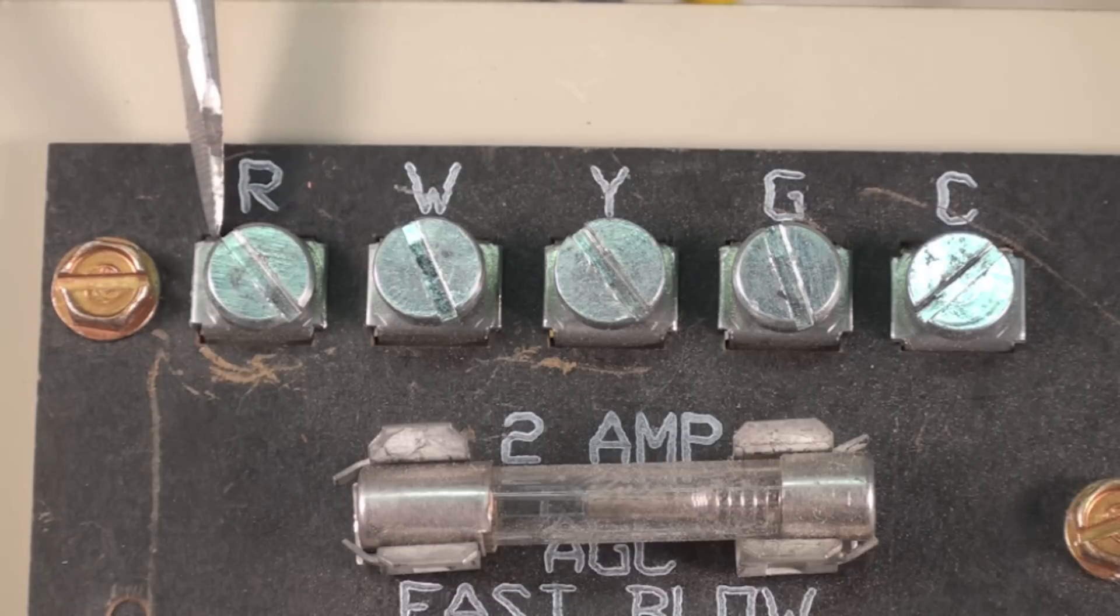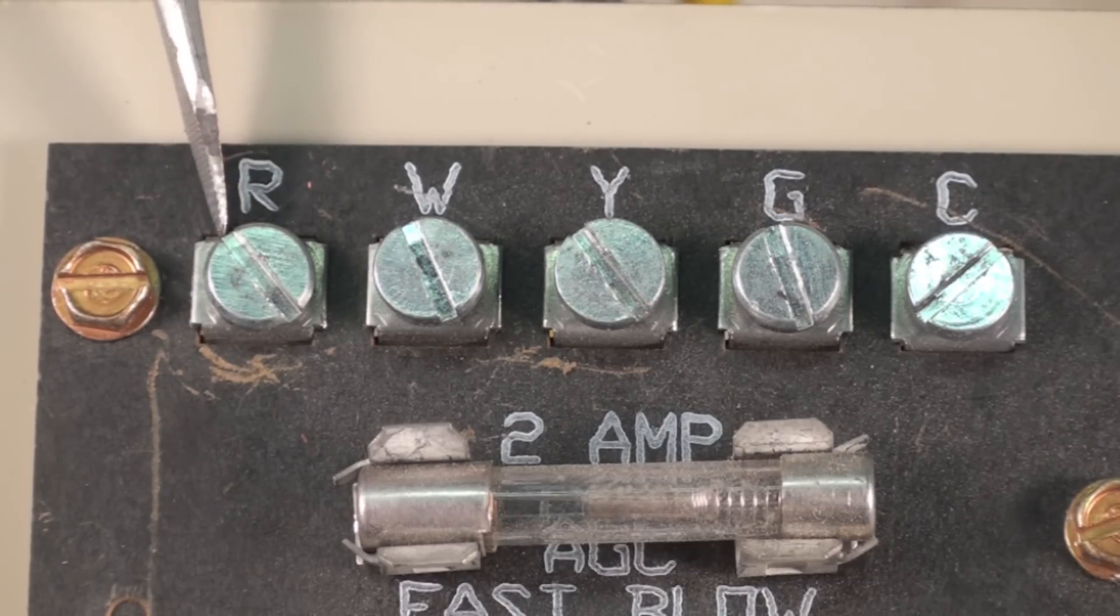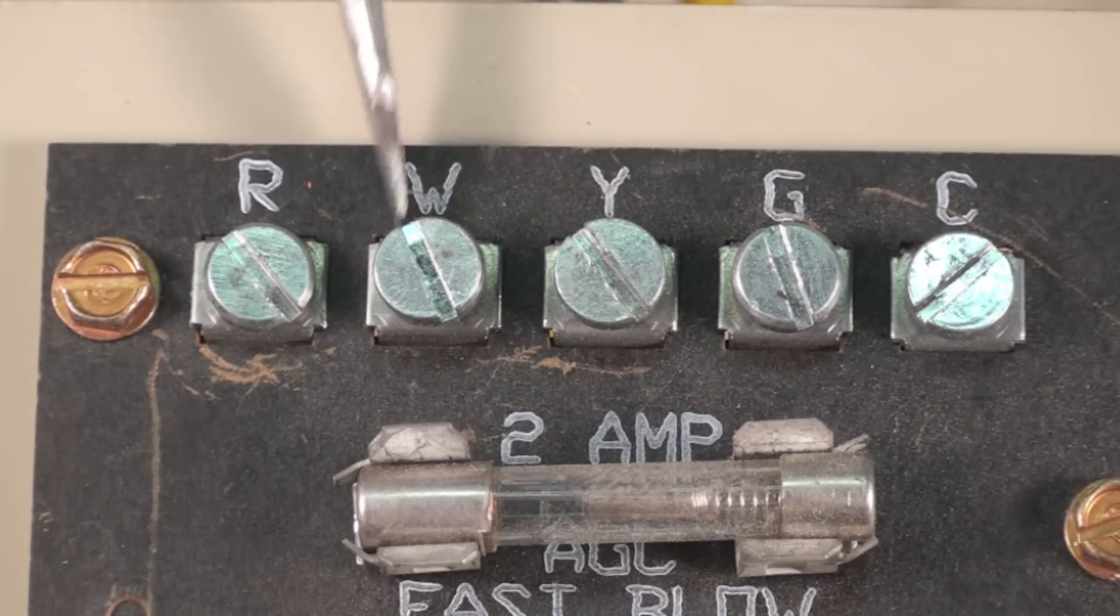So this R would go up to the thermostat and go to R in the thermostat, come out W, which is heat. And so if there was continuity between R and W, you would supply heat signal to the furnace.